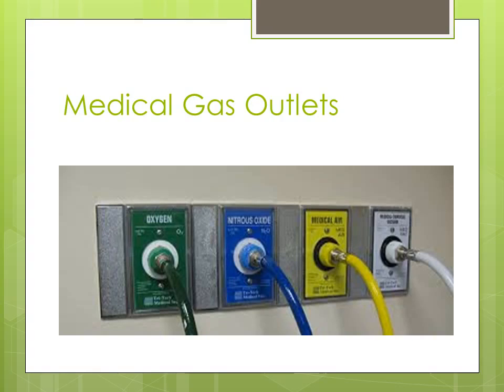Some outlets require different ways to connect them. And where that created problems for us is that certain equipment, particularly equipment used by respiratory therapy, if they were to take a crash cart and they were to have to go to a different unit, they would have to keep multiple adapters or different type hoses to connect to the outlets.